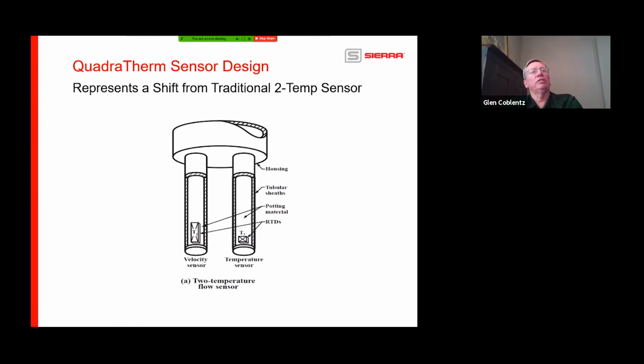We talked about the temperature. In a traditional thermal mass flow meter, you have two temperature sensors. You have one on the velocity sensor, you have one just measuring the ambient temperature. But the velocity sensor is what's being heated up. So all this heat is going up here and heating up the probe. We call that false flow. Everybody else has that problem. And that's why the accuracies are not where they're at, or where they can't match the Quadratherm.